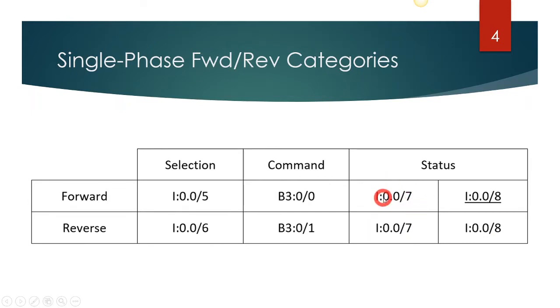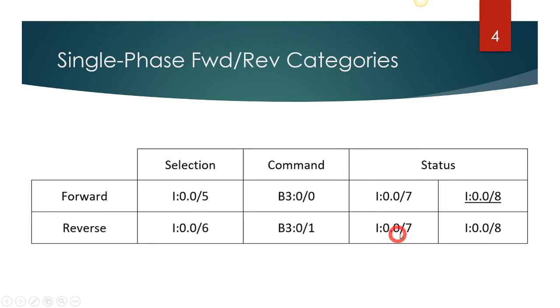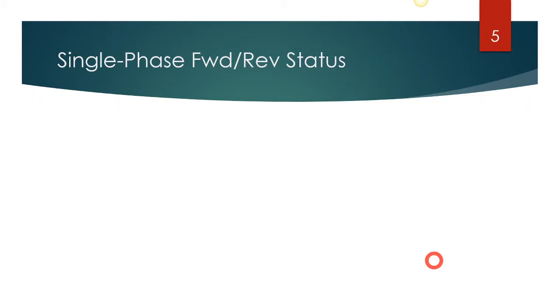Control relay one status comes in at the seventh bit, and control relay two comes in at the eighth bit. Our forward command bit is named 'forward run' — you could call it something different like 'forward command' or 'forward direction.' If CR1 has status and CR2 has no status, that is our forward direction. If CR1 has status and CR2 is also energized, that is our reverse direction status. In the next slide we'll see how to code that and make it look like just one piece of information.